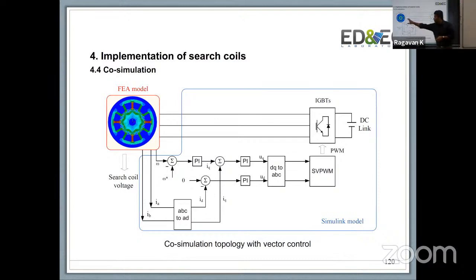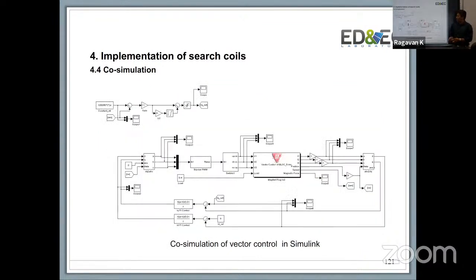So we have search coil voltage that's going in. It has to be processed. The one thing you will notice is that there is always noise. On any signal, anytime you measure the voltage across the phase windings, you are going to get noise. This is no different. You're going to get some noise, which means you have to have a filter that allows you to actually clean up the signal and send that over to your space vector module.